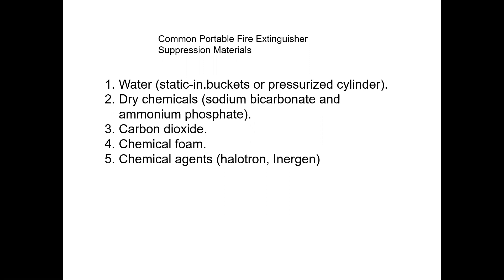We can use water, dry chemicals — sodium bicarbonate and ammonium phosphate are the two basic ones in Class B extinguishers. A multi-combination ABC extinguisher will have mono ammonium phosphate. Carbon dioxide is another option, and chemical foam is common — the fire department uses it regularly. We also have chemical agents: we used to have halons; now we have halotron and Inergen, a European development that's environmentally friendly and doesn't affect the ozone layer.